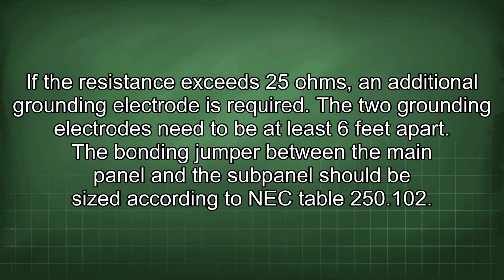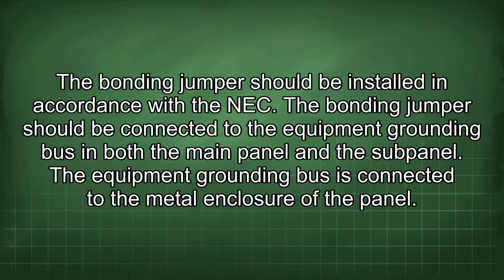The bonding jumper between the main panel and the subpanel should be sized according to NEC Table 250.102. The bonding jumper should be installed in accordance with the NEC. The bonding jumper should be connected to the equipment grounding bus in both the main panel and the subpanel. The equipment grounding bus is connected to the metal enclosure of the panel.